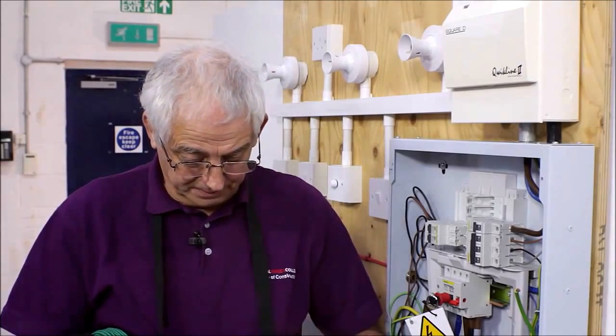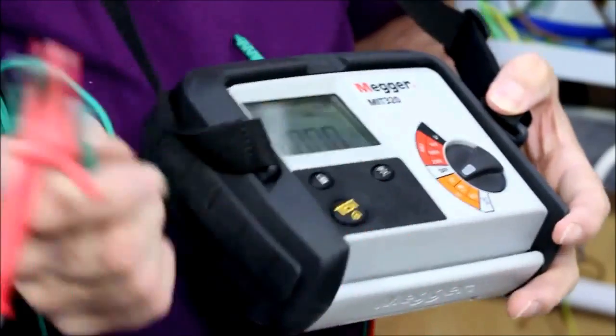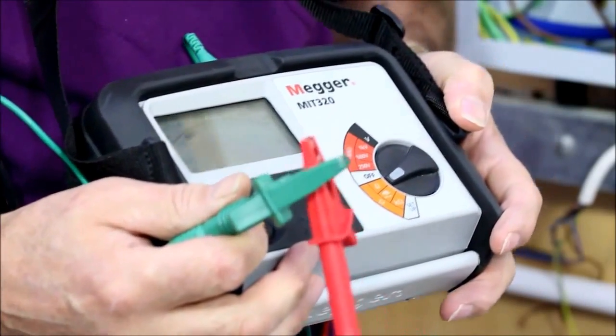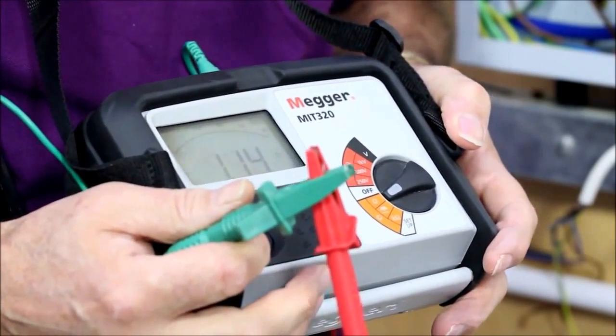Once I've done that, set the tester to ohms, let the machine settle, then I push the button and we can see that I've now zeroed the leads. So any resistance value that I measure now will subtract the value of this lead. Of course, another way we could do it is to measure the resistance of the lead, write it down, take a reading, and then subtract the resistance of this lead at the end of the job. Okay, so we need now to measure from end to end.